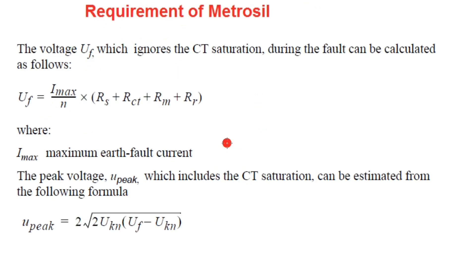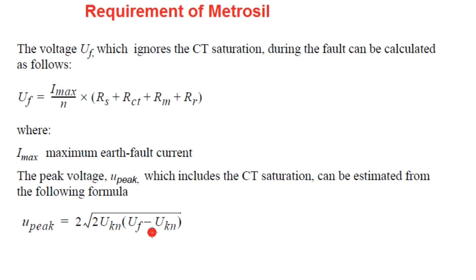To determine whether the metrosil or voltage dependent resistor is required, we first calculate the peak voltage developed under fault condition, given by: Upeak = 2√2 × √(Ukn × Uf − Ukn²), where Ukn is the CT knee point voltage and Uf is the voltage developed under fault condition in the CT secondary circuit.